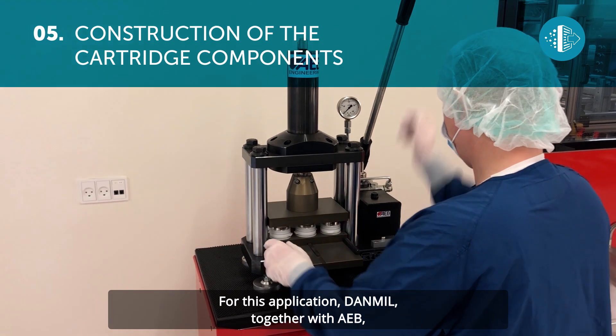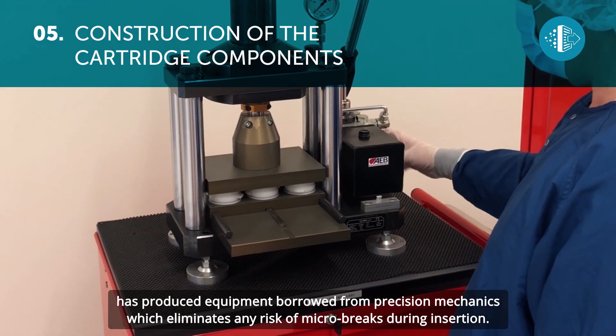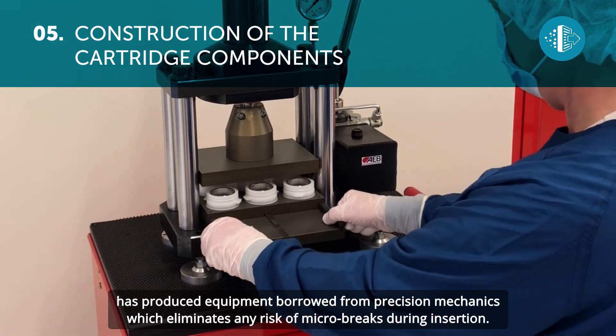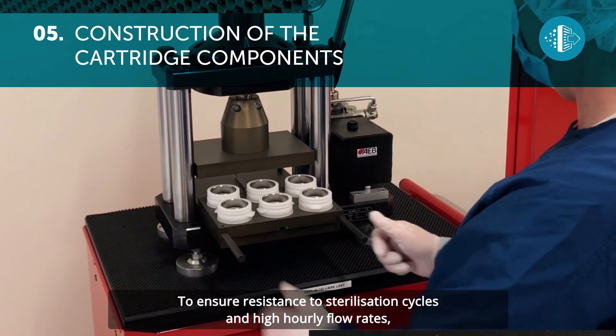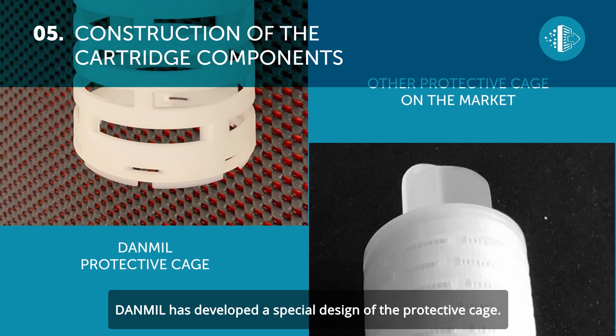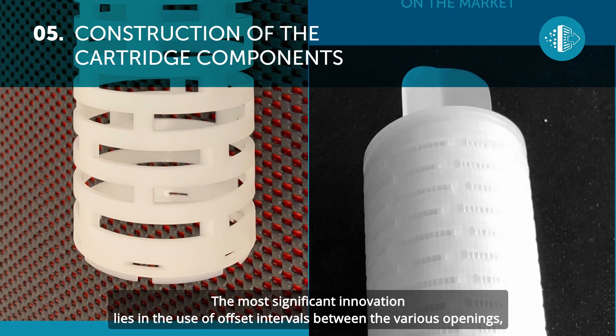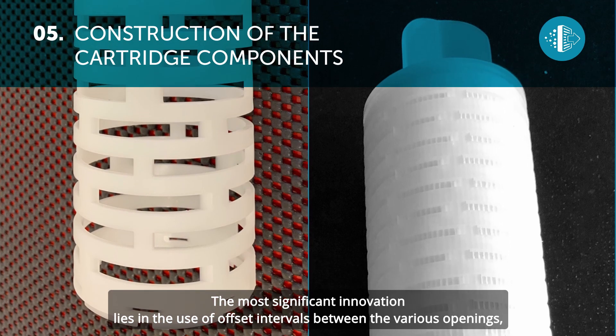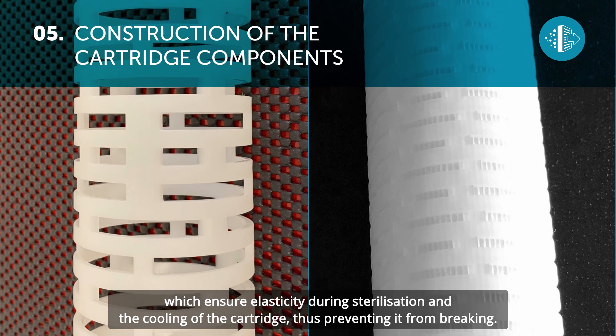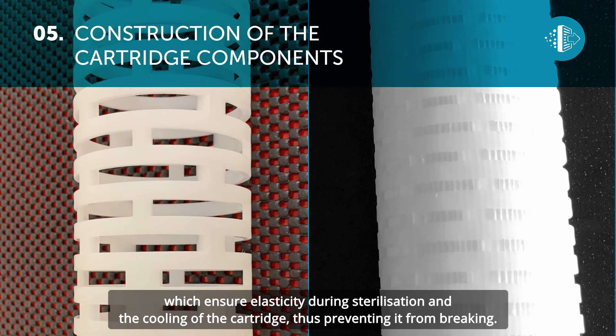For this application, Danmil together with AEB has produced equipment borrowed from precision mechanics which eliminates any risk of micro breaks during insertion. To ensure resistance to sterilization cycles and high hourly flow rates, Danmil has developed a special design of the protective cage. The most significant innovation lies in the use of offset intervals between the various openings, which ensure elasticity during sterilization and the cooling of the cartridge, thus preventing it from breaking.